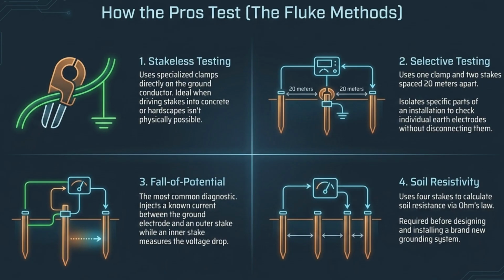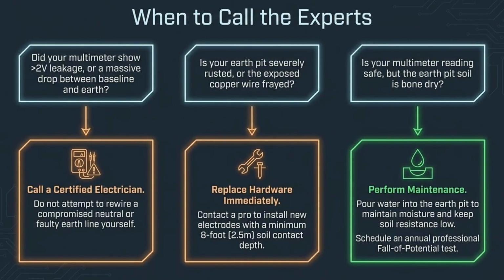Professional testing methods include stakeless testing, selective testing, and the fall of potential test, which is the most common diagnostic for measuring the effectiveness of a ground system. Finally, know when to call the experts. If your tests show significant voltage leakage, damaged hardware, or if your soil conditions are poor, contact a certified electrician immediately to address the issue and keep your home safe.